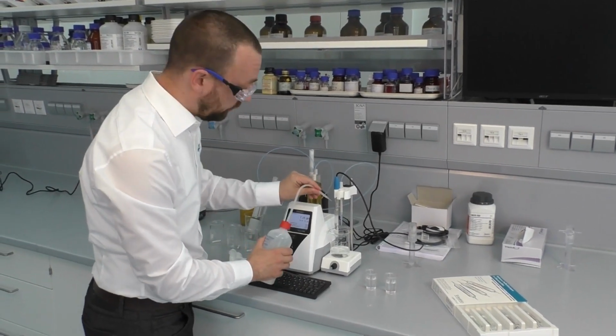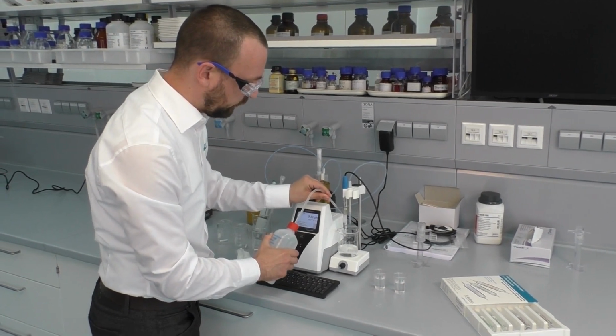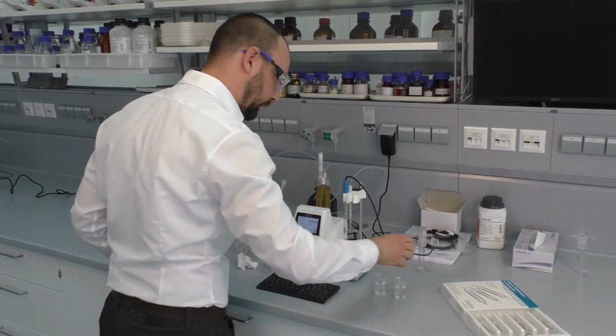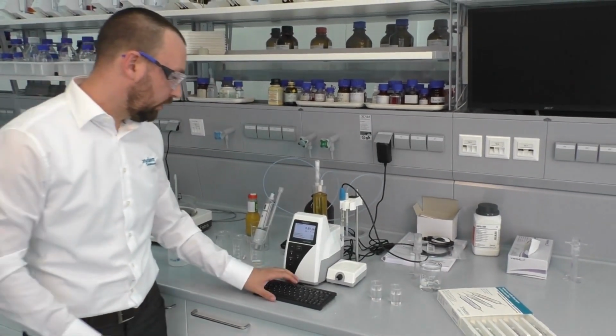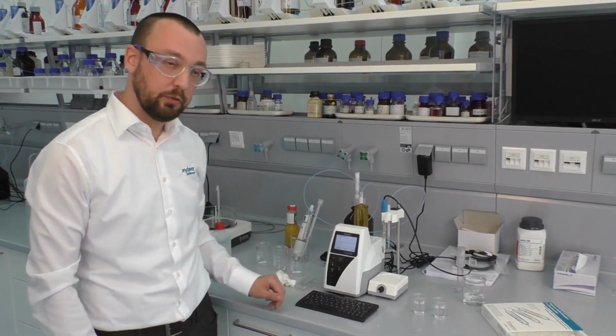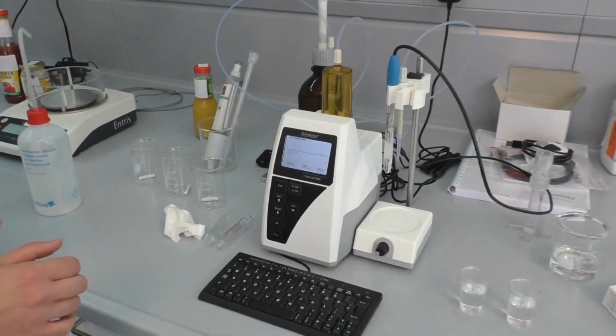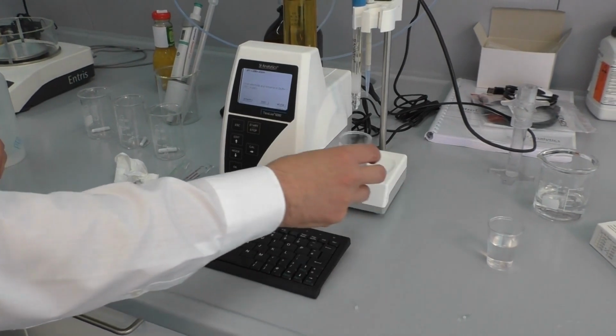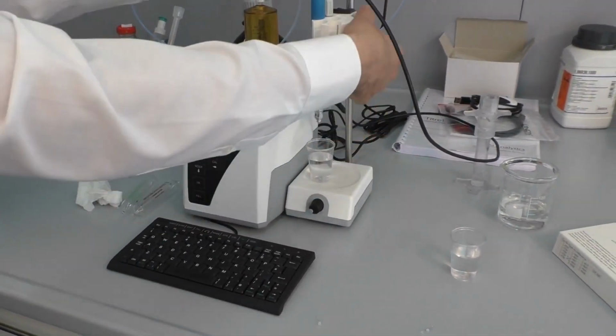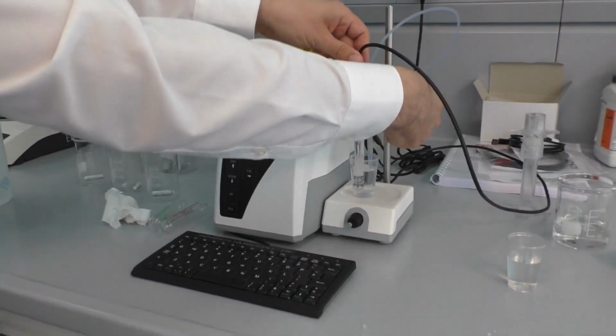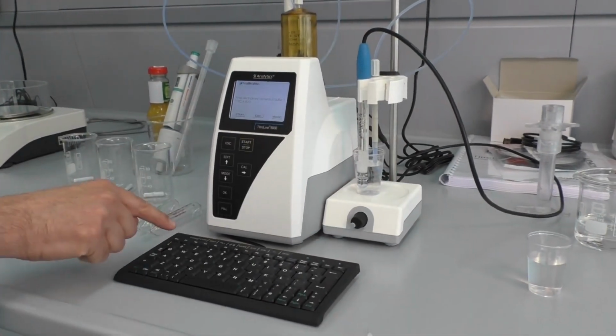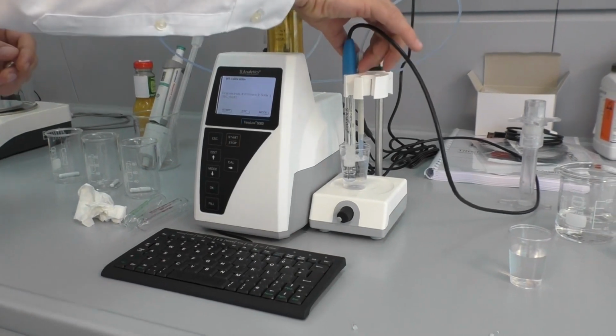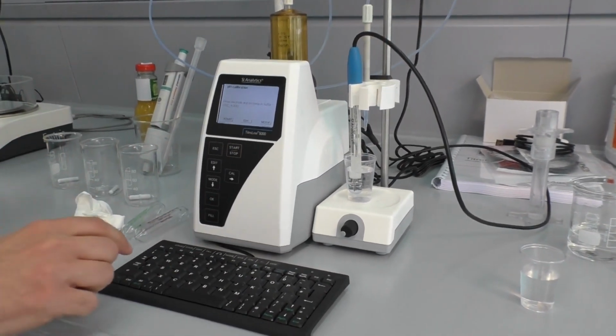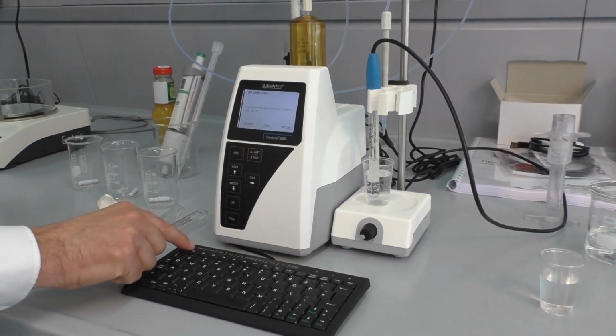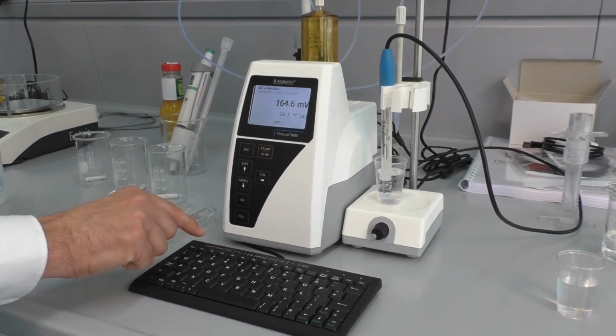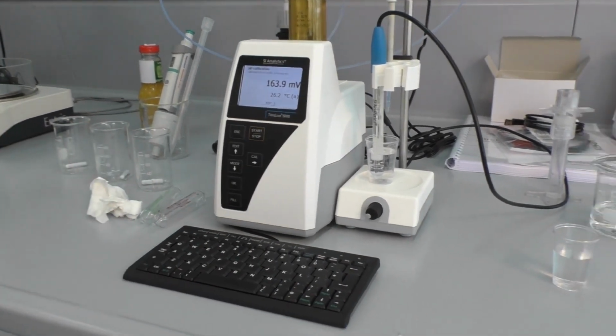The pH electrode is rinsed before the calibration starts with deionized water. Then we go with F8 to the calibration menu of the instrument. The display says automatically which step needs to be performed. In that case, rinse electrode, which we have already done, and immerse into buffer 1, which is the buffer 4. Then we press the start button and the calibration is performed.